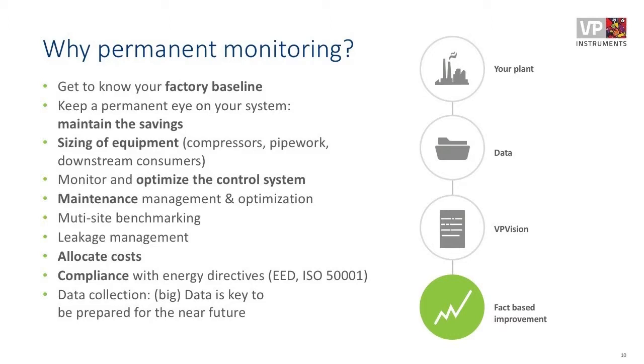Also, if you have a permanent monitoring system separate from control, you can use it to monitor and optimize the control system, or even invest in a different control system at some point without losing all your data, because it's a separate solution, separate from the control. And it might detect some issues which the control system doesn't see or doesn't report. Maintenance management and optimization, I already talked about that. With the monitoring solution, you know where to look for the problems. You know where to go for the biggest leak.